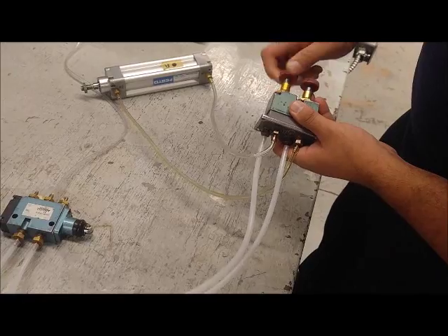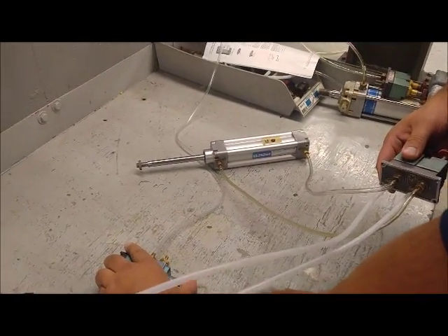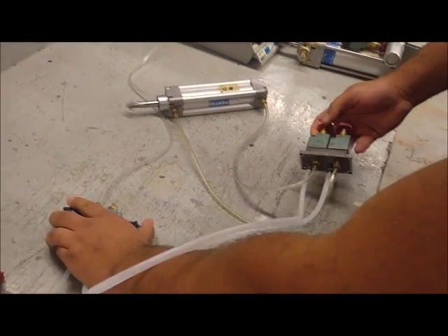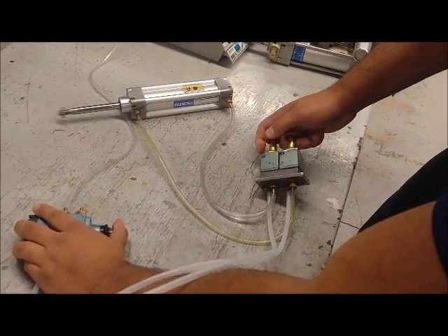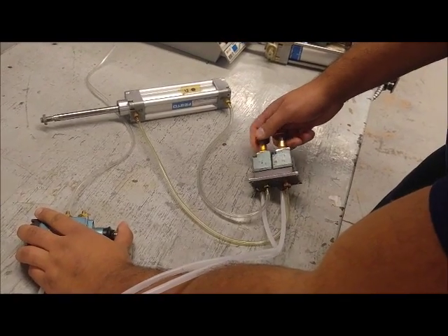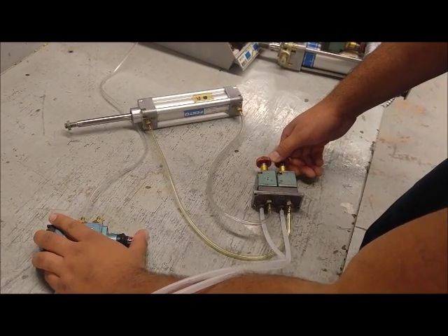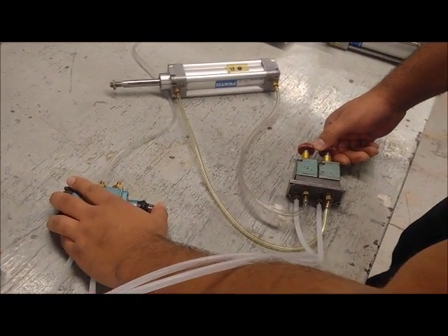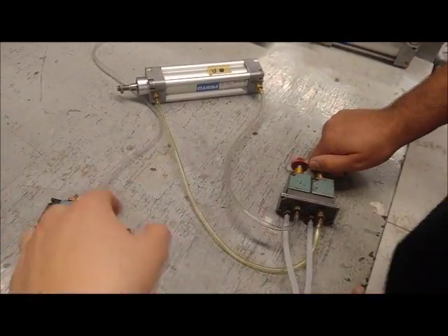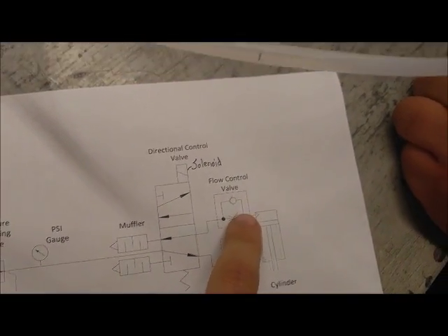So let's go ahead and give it a little tightening up. Not quite tight enough yet. Not quite tight enough. Oh yeah, here we go. Sometimes you need that slow motion. You know what they say, slow motion is better than no motion, right? And you can see how it retracts at a slower speed, but it still extends at full speed. That is because the way the air flows through this valve, it is metered on the way out.